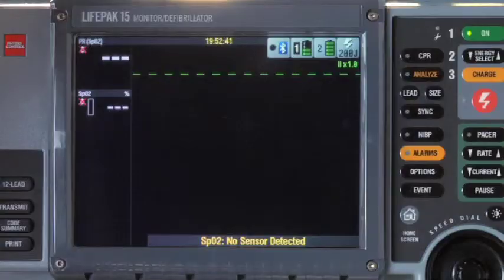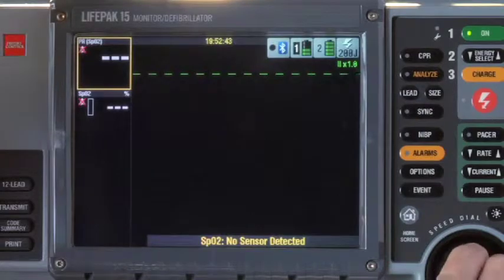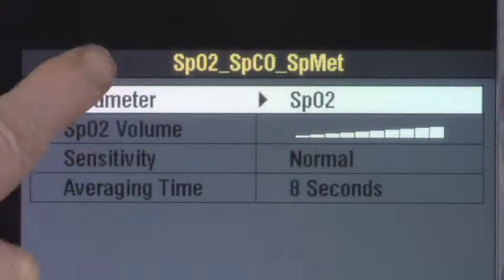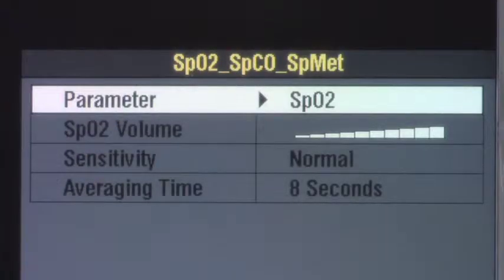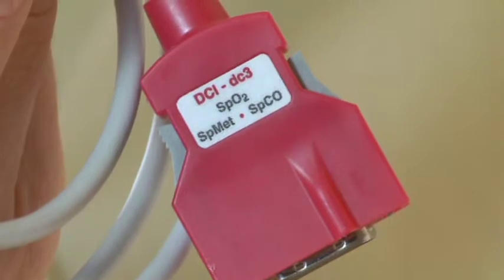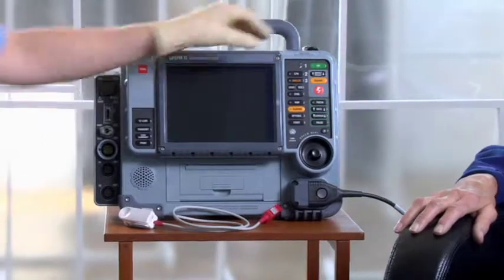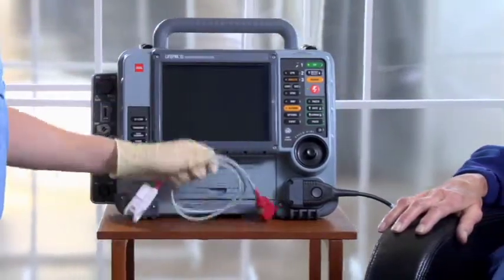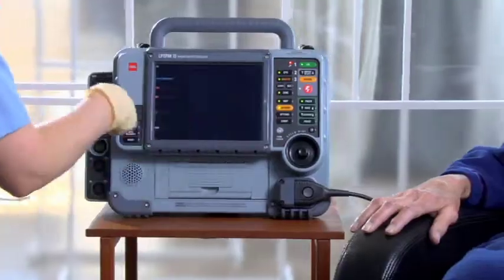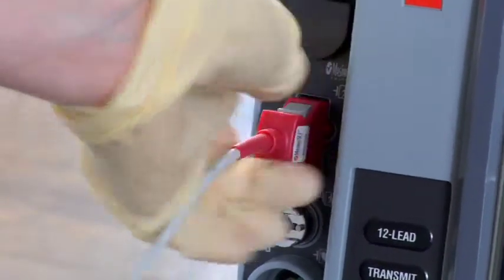The other way to check is to highlight the SpO2 area and click it. You'll see what you have available here. If you want to monitor SpO2, CO, and MET, you have to use a rainbow sensor. If your sensor is only capable of monitoring SpO2, you won't be able to monitor CO and MET. But in this case, both our monitor and our sensor are capable of all three. So, the monitor's on, connect the rainbow sensor here firmly.